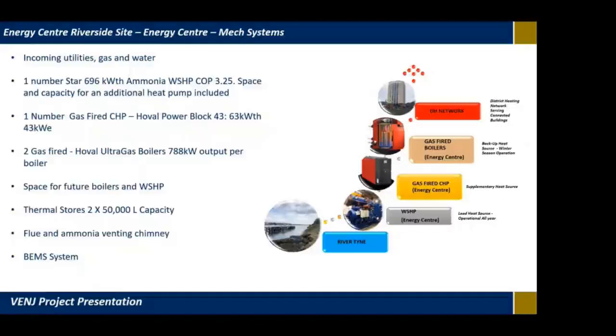So in terms of the energy centre Riverside site, as we call it, the mech systems on the site are obviously incoming gas and water. We've got one water source heat pump. The manufacturer is Star, based in Glasgow. It's a 700 kilowatt thermal unit, just slightly under, 696 to be exact. It's got a COP of 3.25, although that does vary across the season.